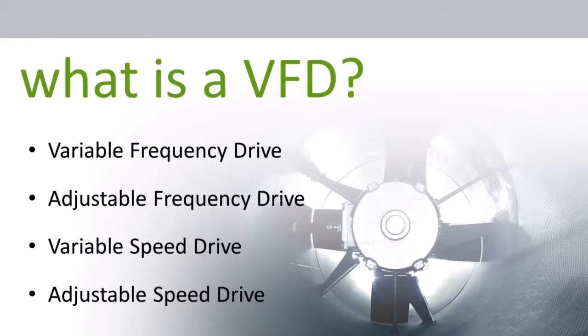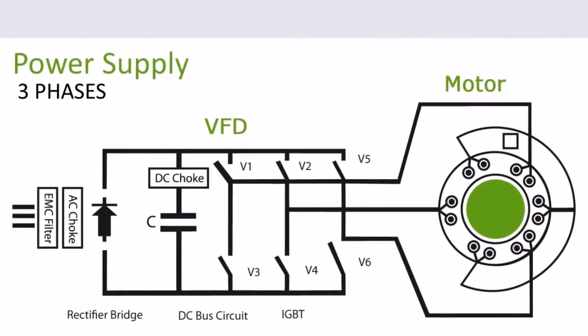All VFDs are going to take three-phase AC power and convert that three-phase power to DC power inside the drive and pulse it out in a simulated AC waveform to the motor. The motor still thinks it has AC power, but the DC power conversion now lets us control the speed of the motor without harming it. Now we are in control to save energy and money.